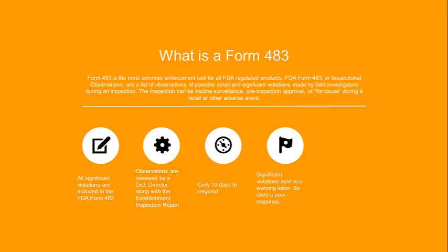And it's often that you'll see in that response, yes, we've seen the observations, and yes, they're corrected. And the FDA says that simply doesn't make sense. So a quick response, and one that isn't thought out, can also lead to warning letters.